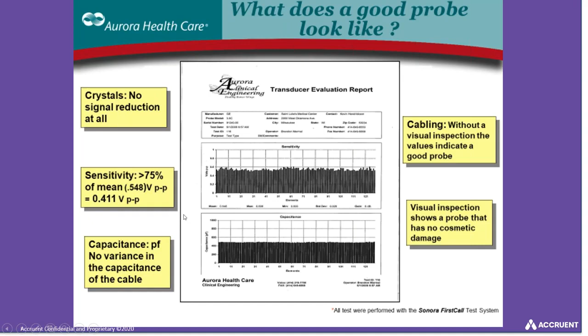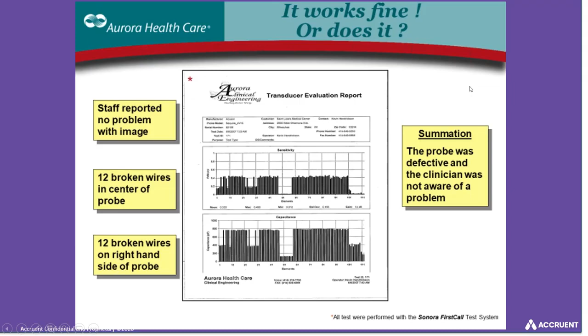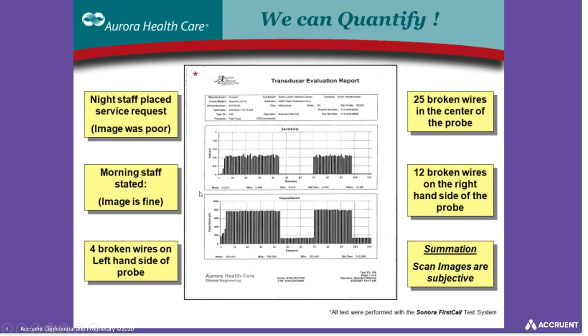So again, we did a baseline of each probe with regard to crystals, sensitivity, capacitance, cabling, and visual inspection. Here's a probe that, according to the sonographer, worked fine, but when we did quantitative analysis of it, found that not so fine. And the thing about transducers or probes as well is it's key where those defects are, and if they're in the middle of the probe, that's where you're going to see the most degradation in image. And again, here we have the ability to quantify these things.